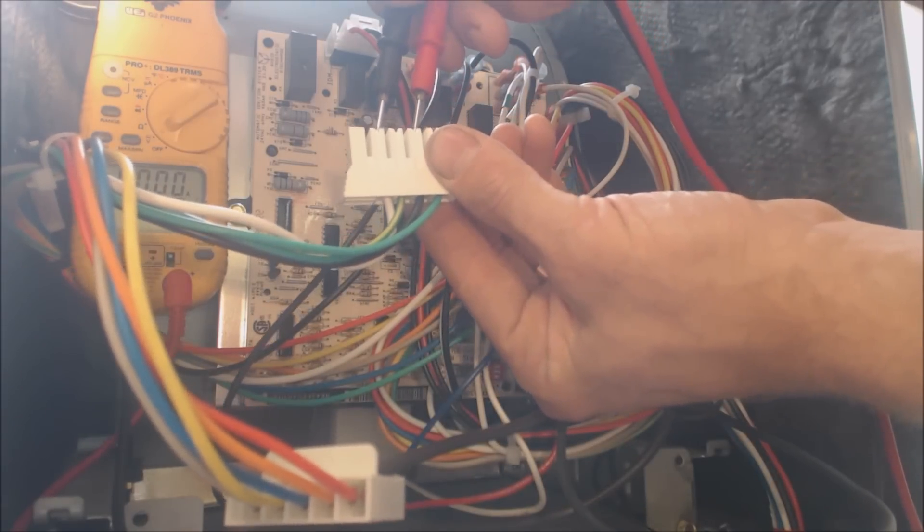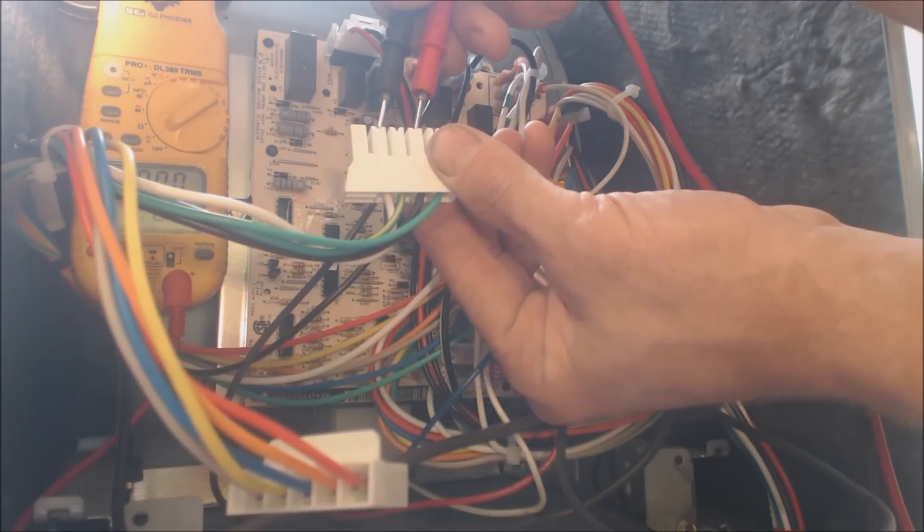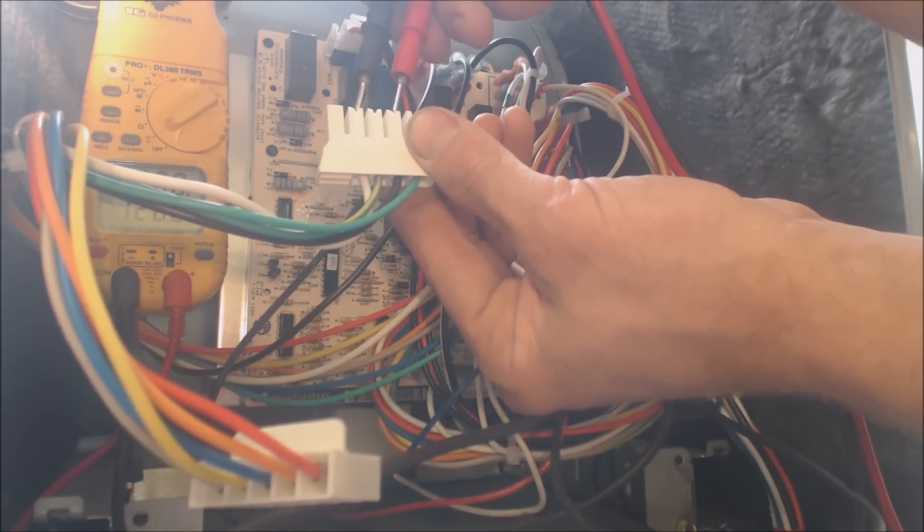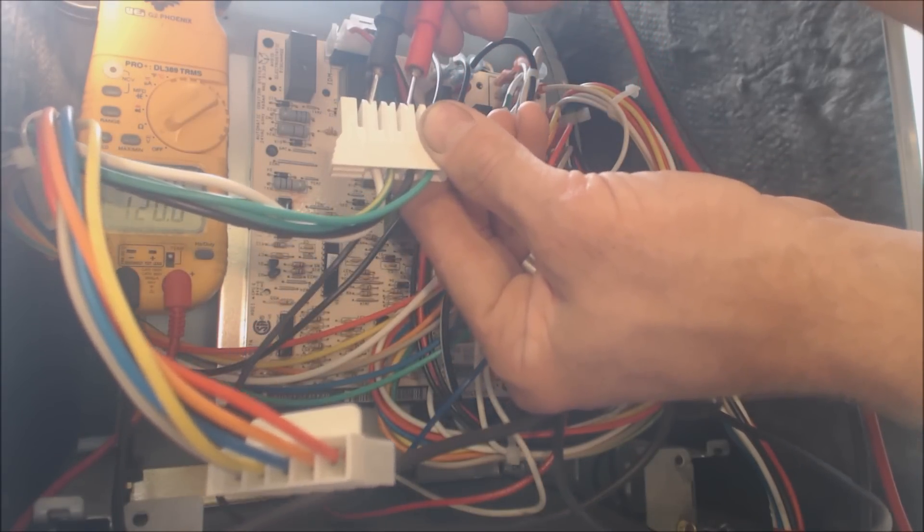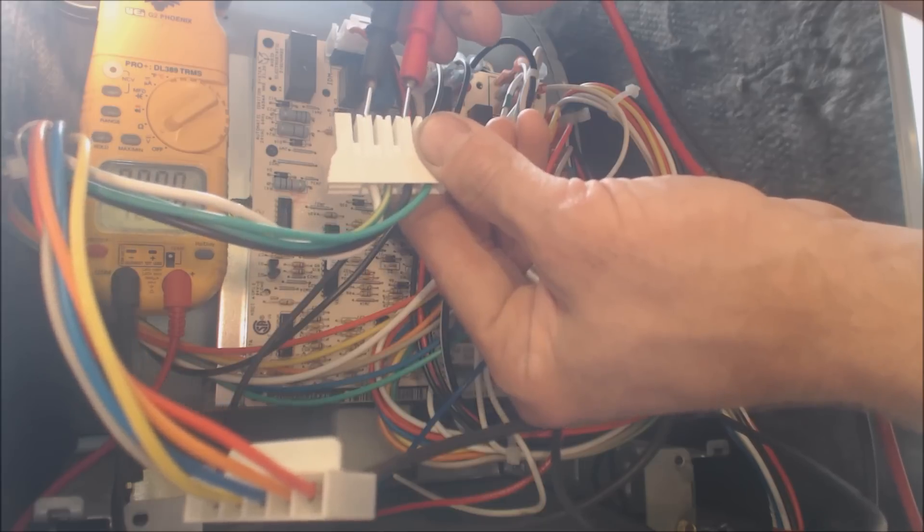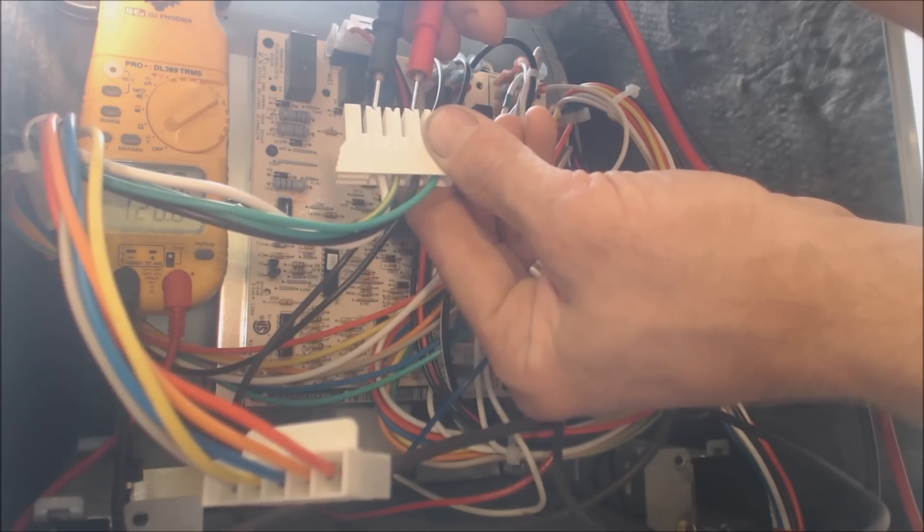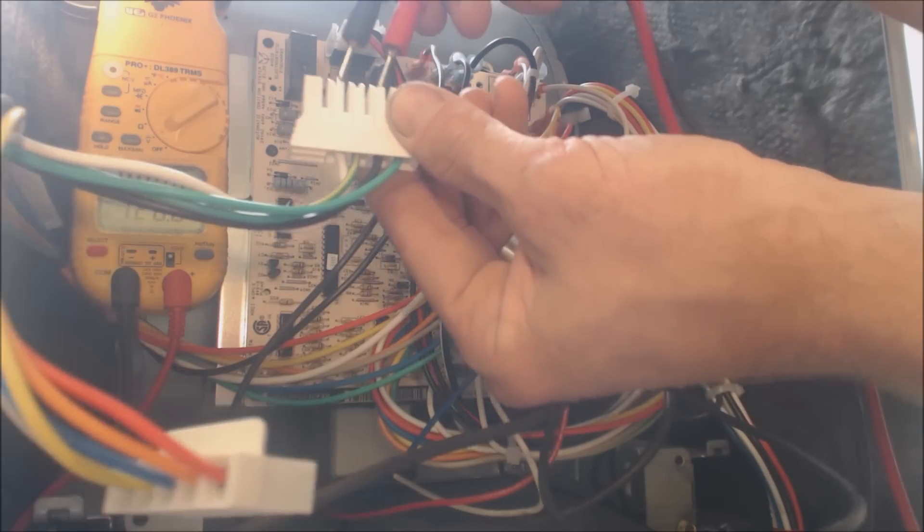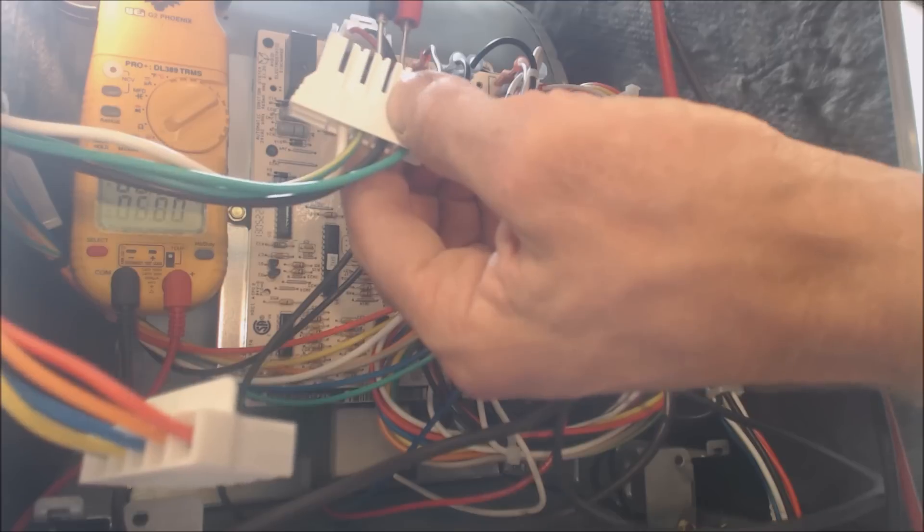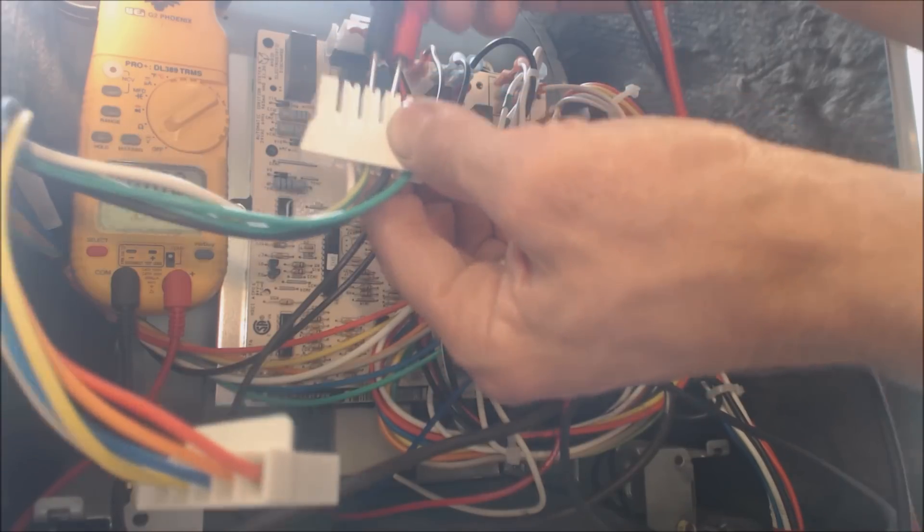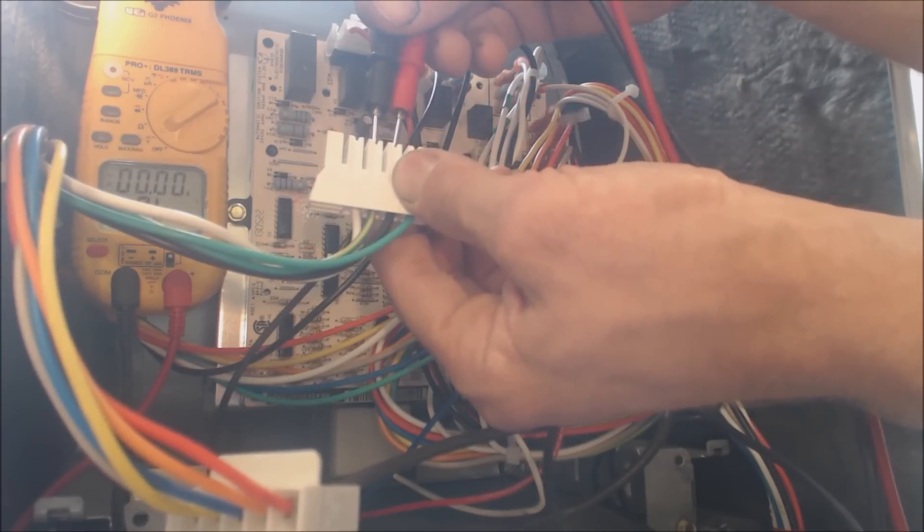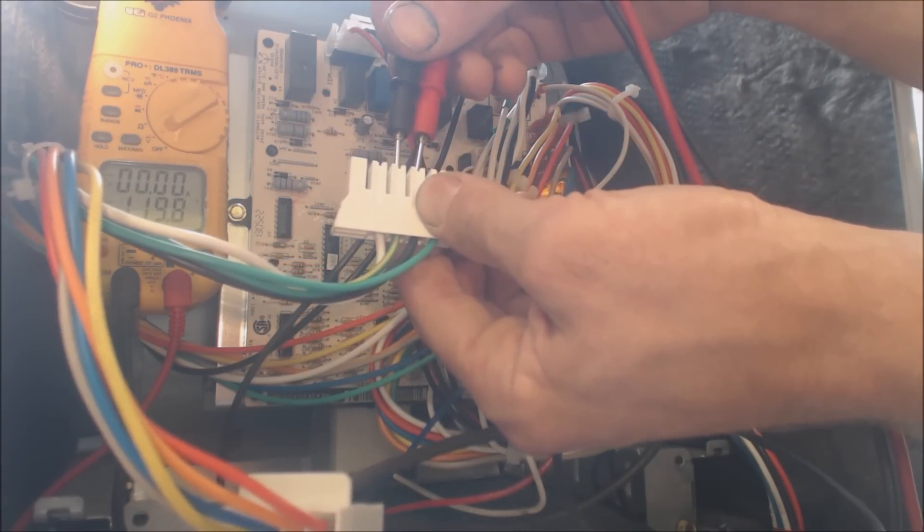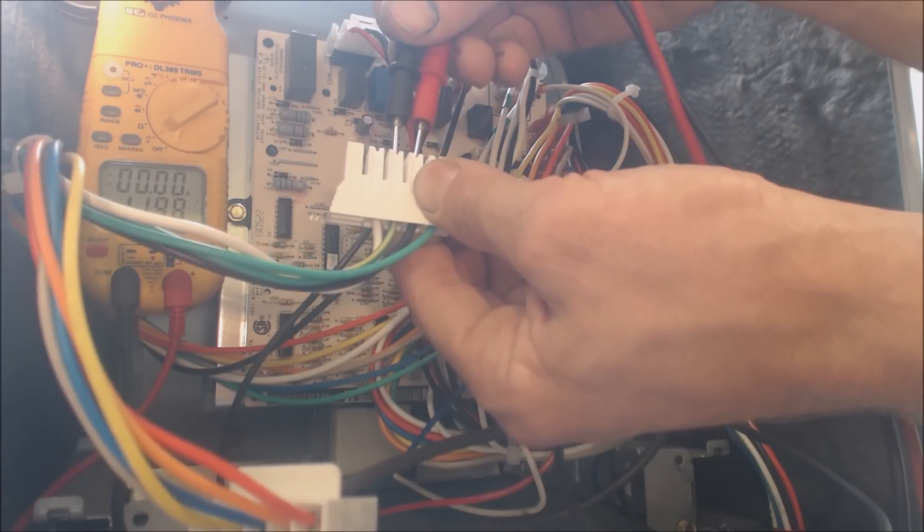We know that we have 120 volts here between the white and the black, and that would be connected in your blower motor. If we just check for instance from ground to black, once again, 120 volts.